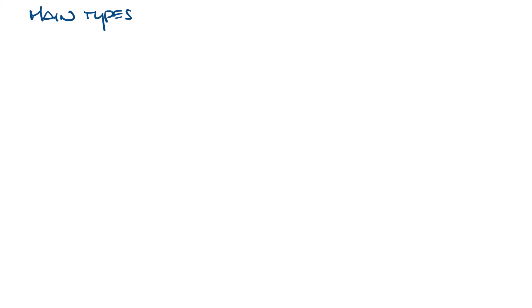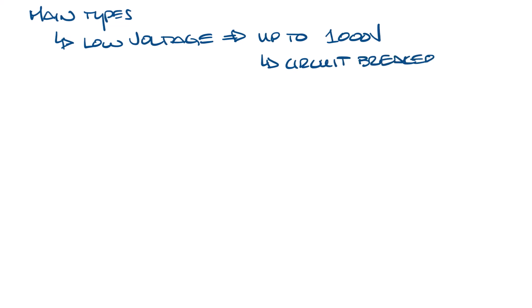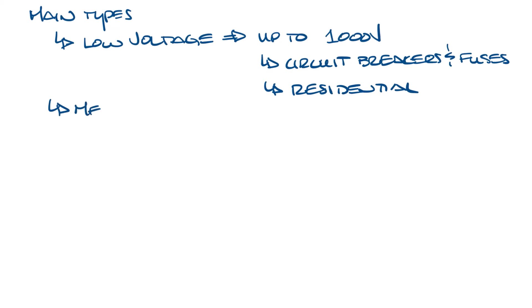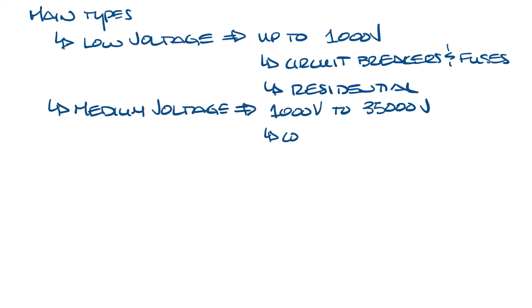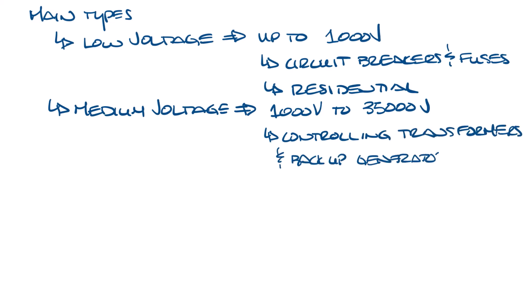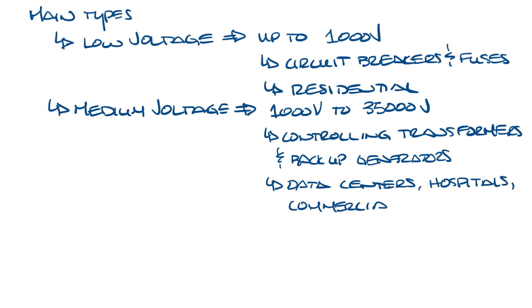There are three main types of switchgear used in buildings and data centers. Low voltage switchgear is used for systems up to 1,000 volts managing power within the facilities — examples would be circuit breakers and fuse panels, which you're probably familiar with from your home. There's also medium voltage switchgear, which handles 1,000 to 35,000 volts, often controlling transformers and backup generators. You'll see these in data centers, hospitals, and other commercial and industrial applications.